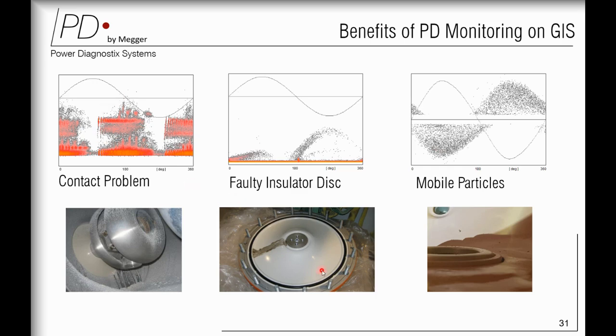This is one location where the customer had used some solution, and when the GIS was energized, there were some bubbles inside which created voids. So this is the PRPD pattern of multiple voids with a faulty insulating disc. Whereas a mobile particle means some small particles left inside during commissioning. When your GIS is energized, they keep dancing inside. This is known as a moving particle. You will get this type of PRPD pattern for moving particles.